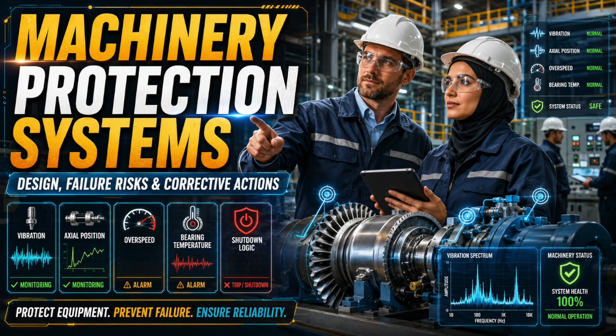Now, circuit faults. A circuit fault is not just an instrumentation nuisance. In machinery protection, a circuit fault means part of the protection layer may be impaired. A failed probe, open circuit, short circuit, failed accelerometer, failed power supply, failed monitor channel, lost communication, or bad transducer can reduce your ability to protect the machine. So circuit faults must be visible, they must be annunciated, they must be acted upon.